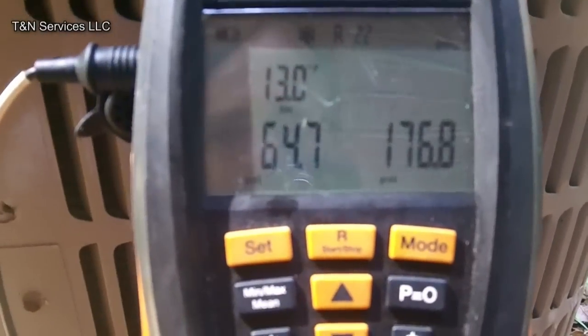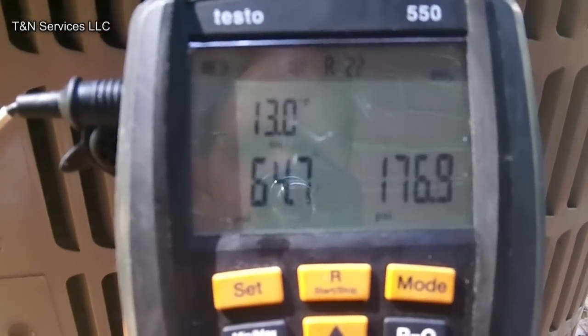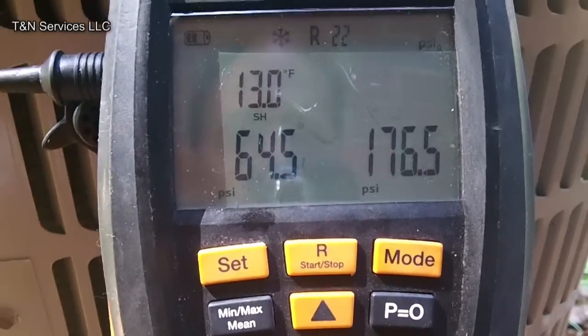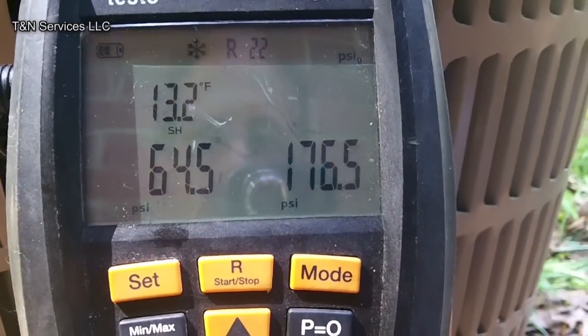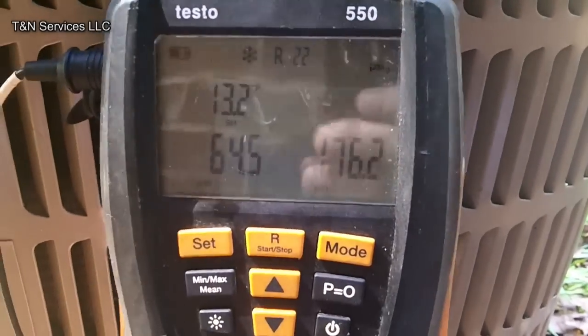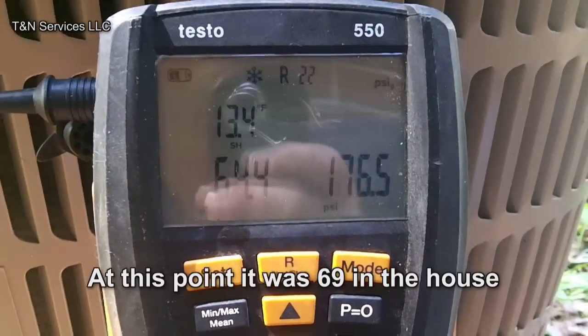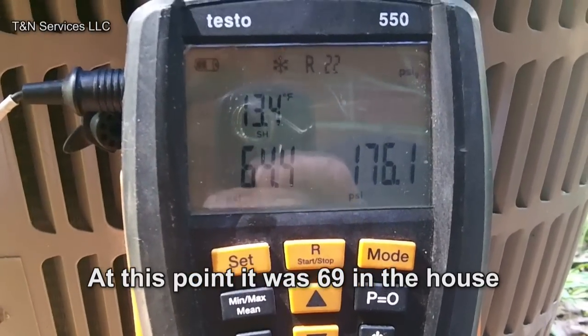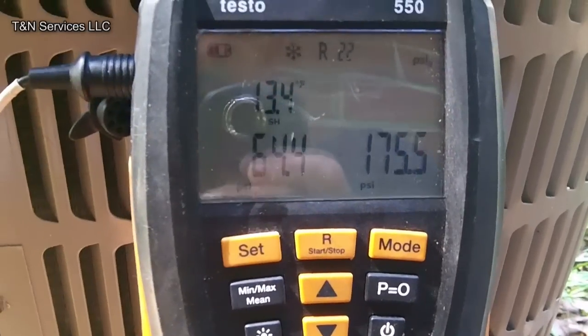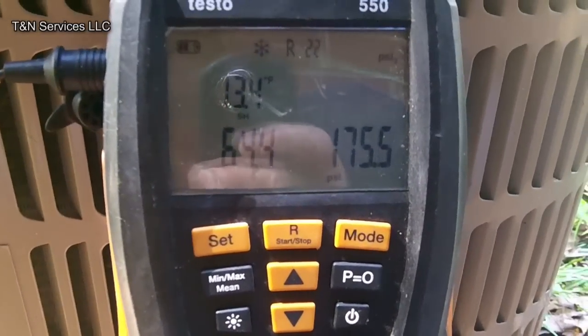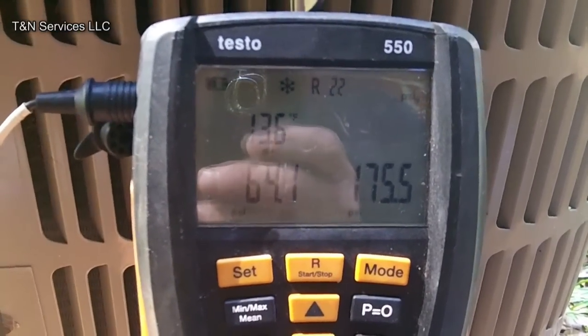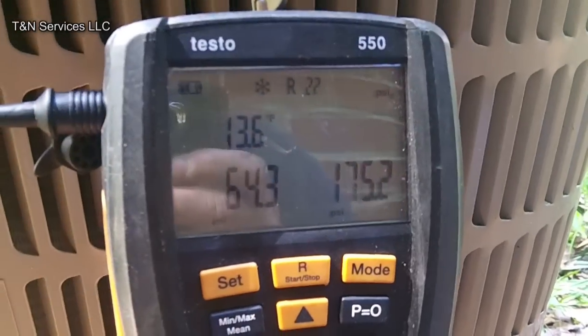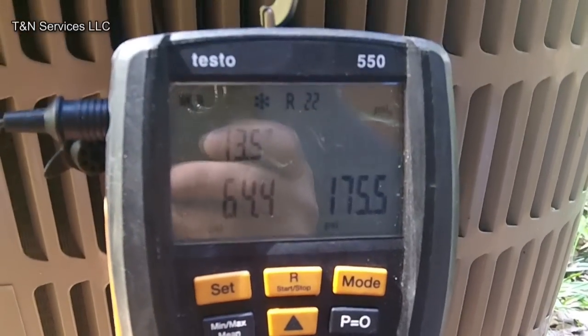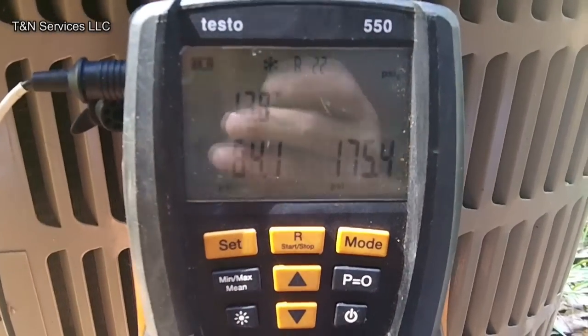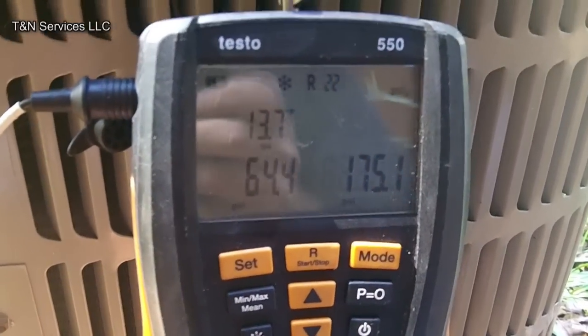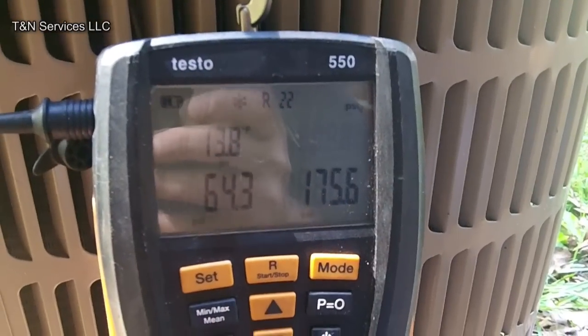Alright, so I got everything set. We're at 13 degree superheat, 12.8, 13, 64.7, 176 head. That's not bad for a house built in 1961 using 1961 ductwork. A 3-ton system that when I got here last night, the house was 83 degrees and getting hotter. So now I'm going to go in there, check airflow at some ductwork at some supply registers, and tell her to get her second blanket out for tonight.